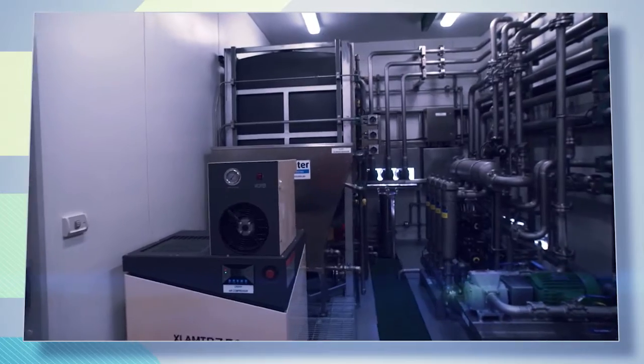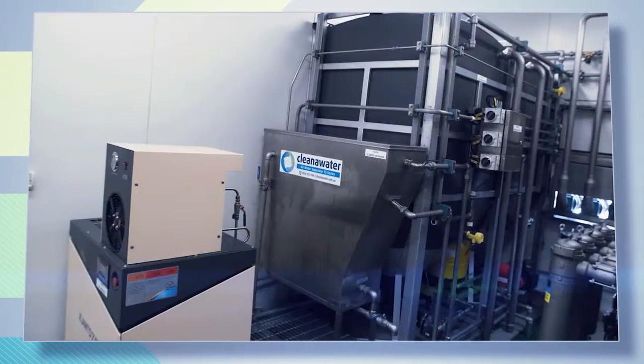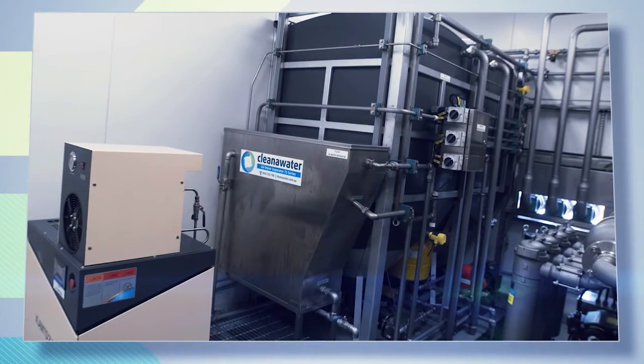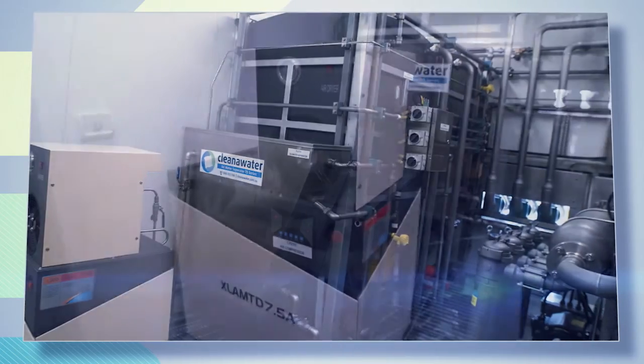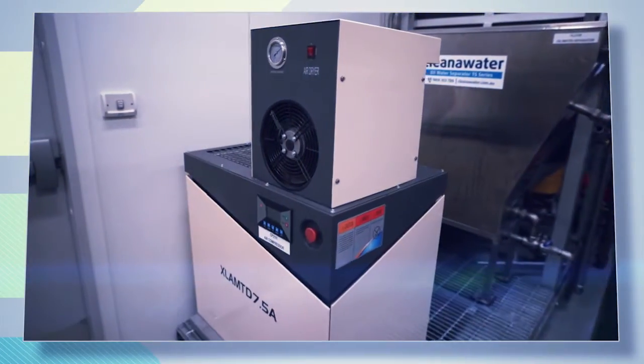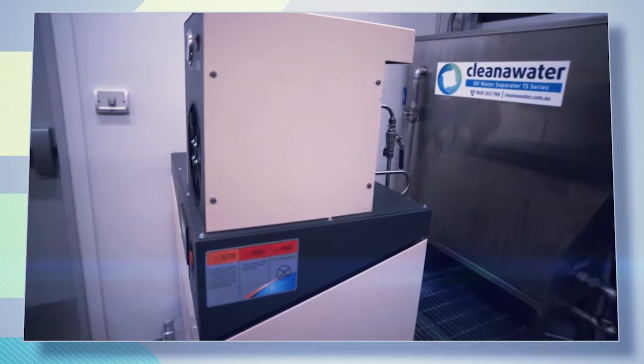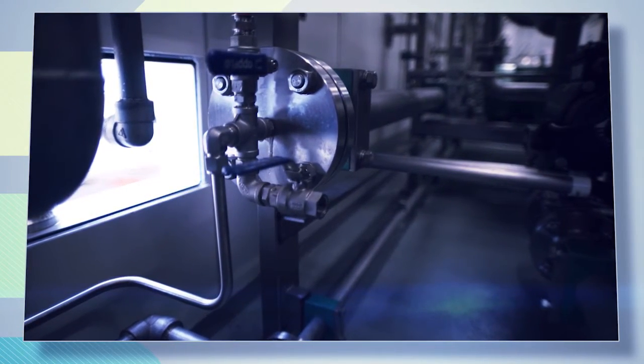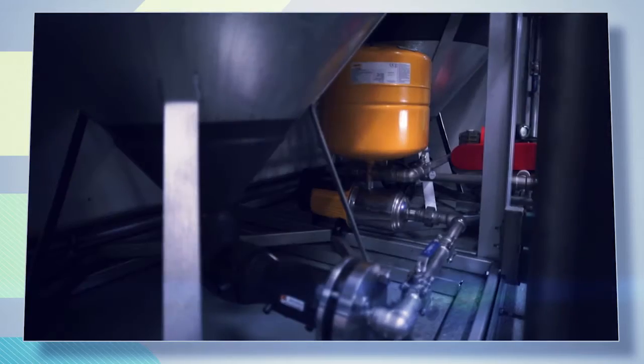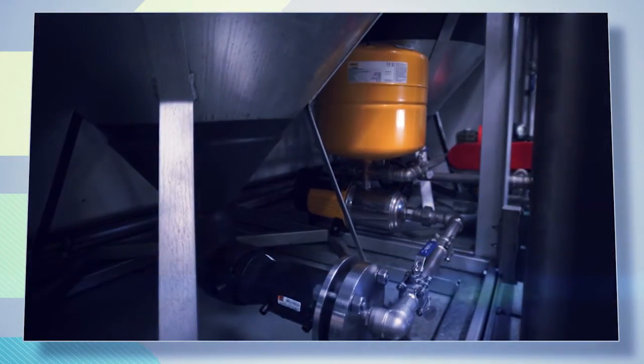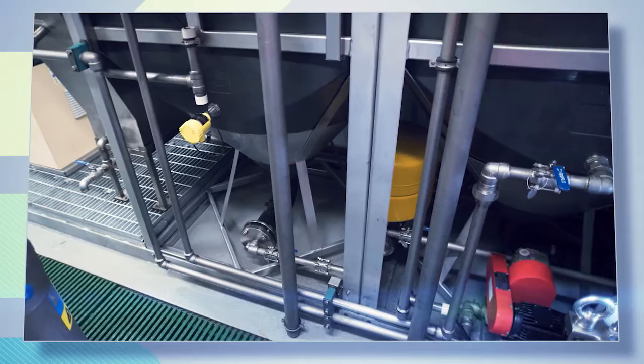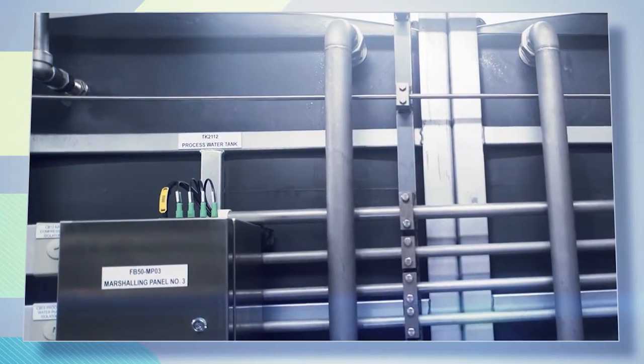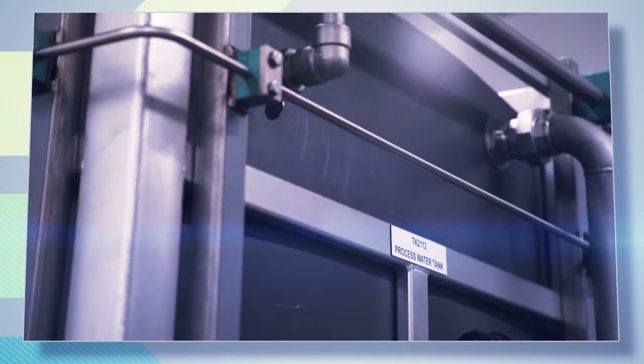The auxiliary and waste systems are modular in design and can be scaled to suit the specific requirements of each site. A self-contained screw-type compressor and dryer can be provided for maintenance activities. An oversized instrument air header provides additional storage capacity. Process water is used for centrifuge bowl operations and fuel washing. A 2,000 litre storage tank, pressure pump and accumulator can be provided.